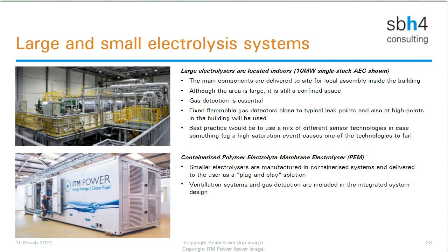But there's a huge difference between the system at the top and the system at the bottom in terms of scale, but fundamentally in terms of gas and flame detection requirements, a huge number of similarities. We basically have hydrogen being produced, a flammable gas, potentially explosive gas. Also oxygen is produced on the electrolyzer, which we may wish to detect for. And whether it's a big electrolyzer or a small one, the gas detection requirements are fundamentally quite similar.